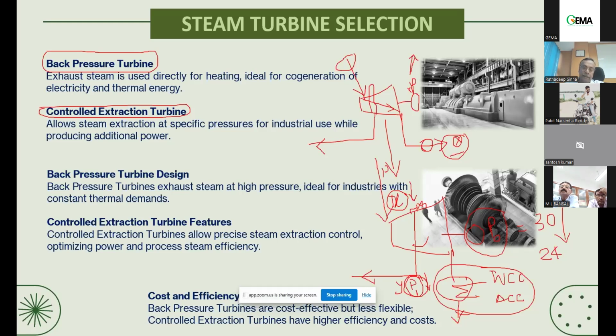For your drying system, this can be configured for a larger capacity plant. Here we can have 6.5 kg pressure control extraction going to the distillation system, and 3.5 kg pressure equivalent going to the drying section, with a pressure drop of course. So that can be configured in a back pressure turbine also.